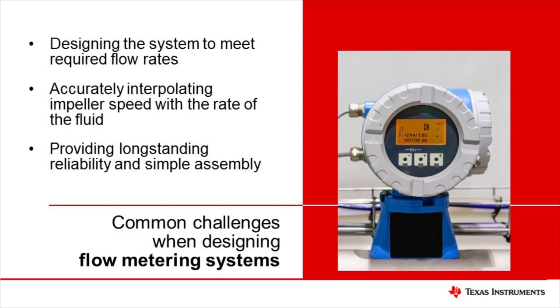Additionally, the force of the liquid flowing through the meter must overcome the initial frictional force of the bearing in order to begin moving the impeller, thereby establishing the minimum flow rate that can be handled by the meter. Other mechanical errors can come in the form of magnet placement. Magnets should be equally spaced and mounted planar to the top of the impeller. Errors in placement can lead to errors in the speed calculations.